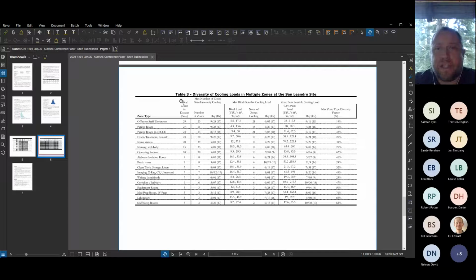The next graph looks again at the diversified load. You can start to see one of the things we were trying to find out is, as design engineers practicing and designing systems that support these room types, as we apply a diversity factor or look at a block load, how close is that estimation to real life?